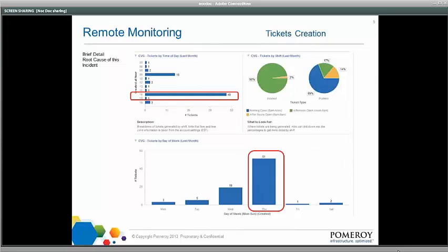For brief detail, Glenn, I've highlighted a couple of events. There's 49 tickets around 4 o'clock p.m., and that was where the 6509 core switch, at least the secondary one, had a power failure. And that generated a number of children tickets where the uplinks were then lost downstream from those items. And so that happened on a Thursday afternoon about 4 o'clock. You can correlate those two events together and be able to see what the incident was.